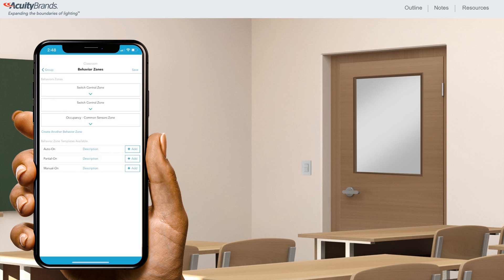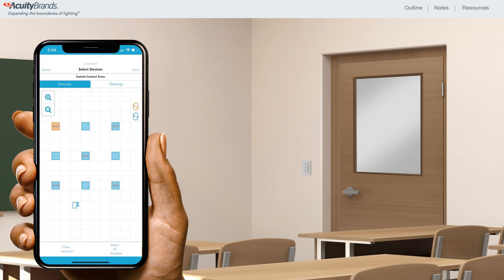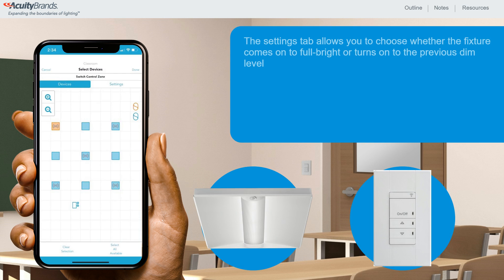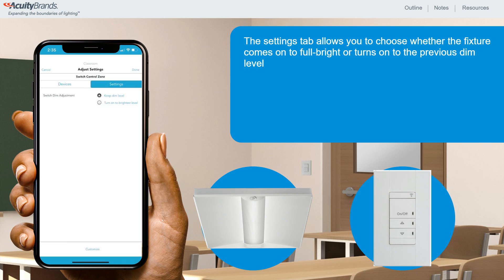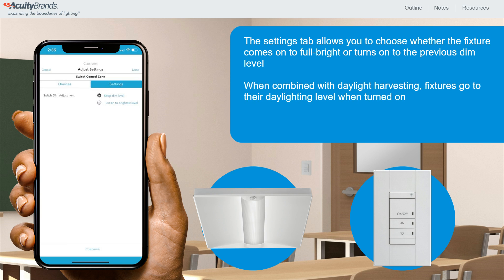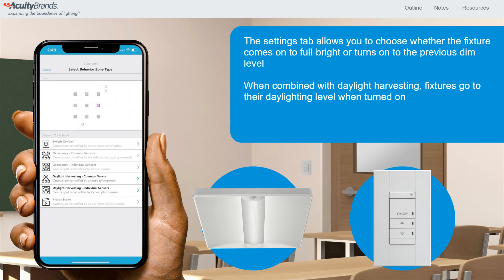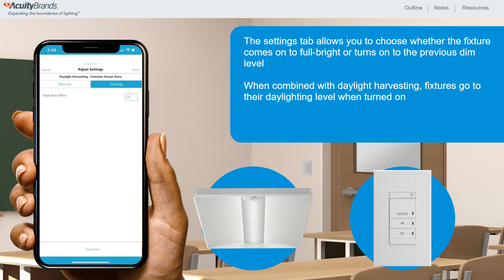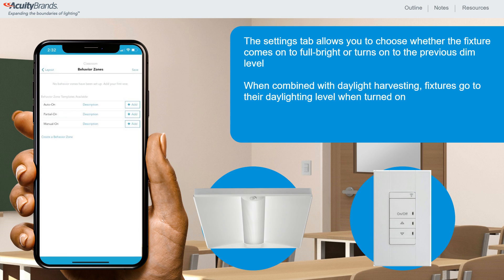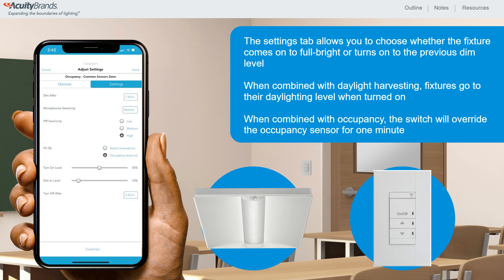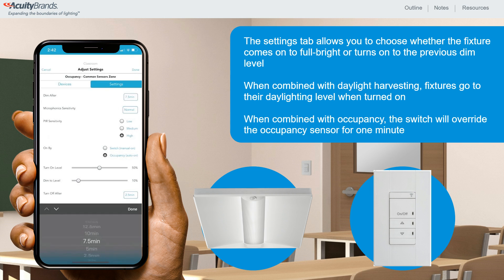Switch behavior zones can be applied to any group that has at least one fixture and one switch. The Settings tab allows you to choose whether the light comes on to full bright, or if it turns on to the previous dim level when the on button is pressed. If combined with daylight harvesting, turning the lights on will make the fixtures go to their daylighting level, and if the switch has raise and lower buttons, the user may raise the light level above the daylighting level. If combined with occupancy, the switch will override the occupancy sensor for one minute even if the occupancy sensor has timed out.